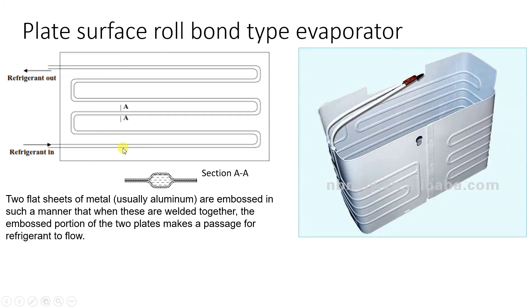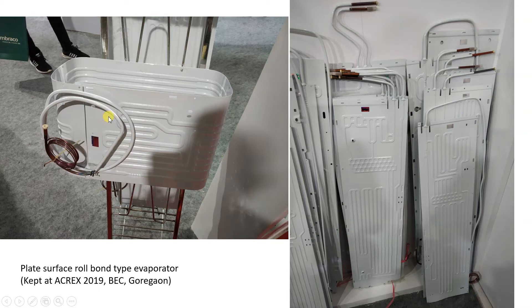Looking at the cross-section, the inflated passage is not exactly a tube — it is a passage formed between two aluminium sheets. Inside this passage the refrigerant flows. The roll bond evaporator is initially manufactured as a flat straight sheet and then bent into a box shape, after which it is fitted into the freezer compartment of the refrigerator.